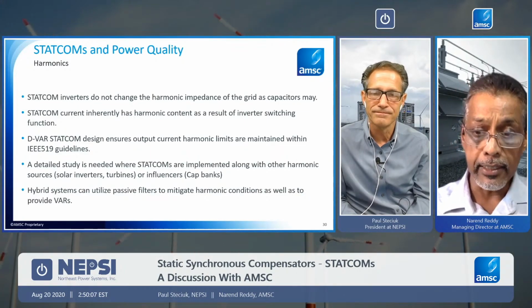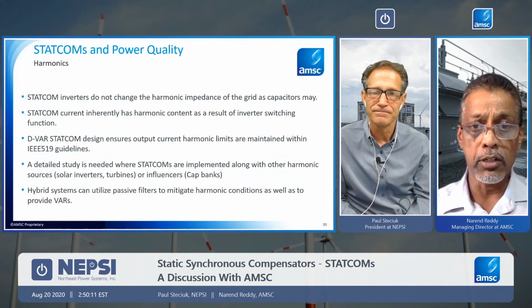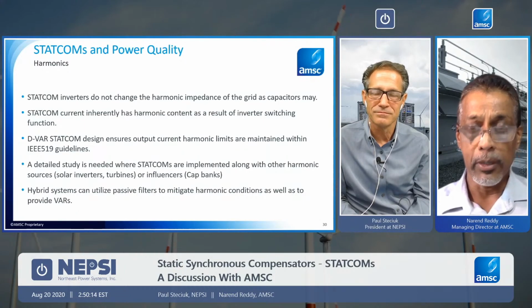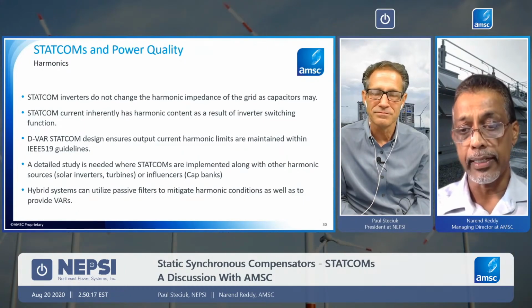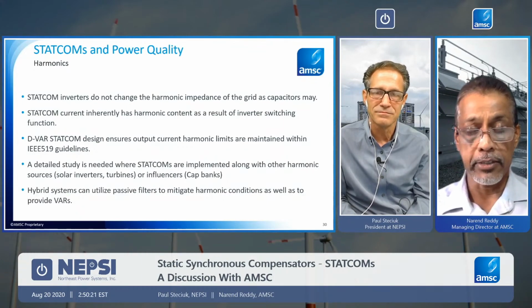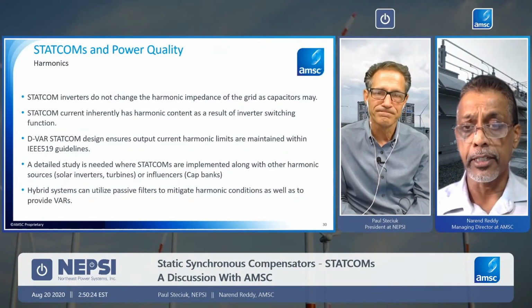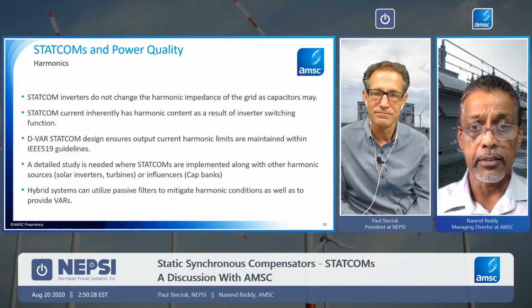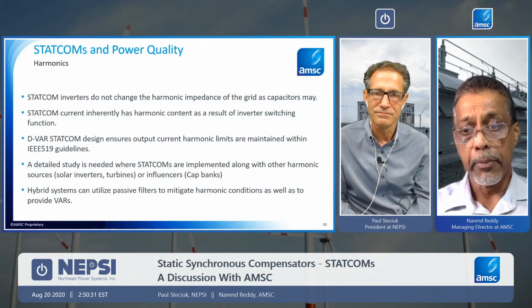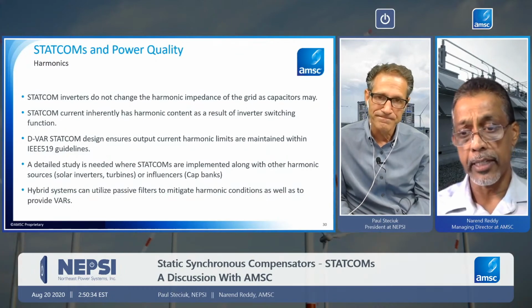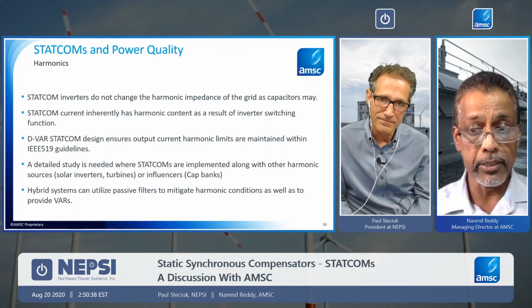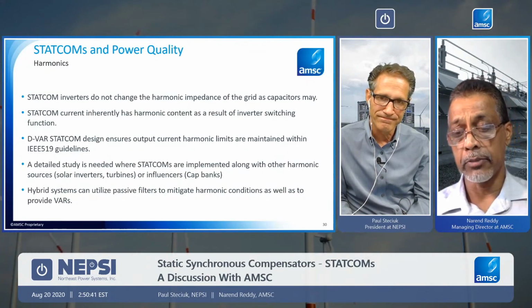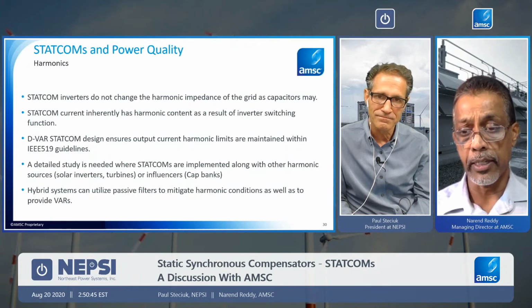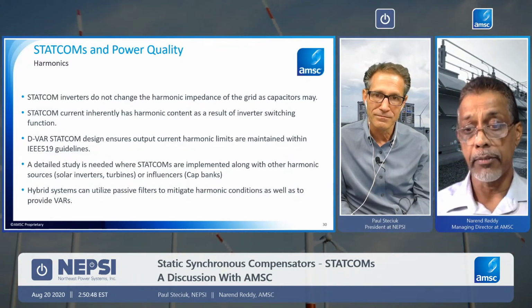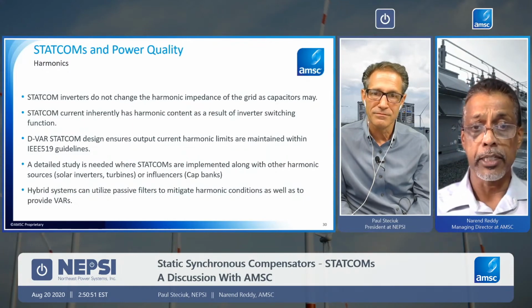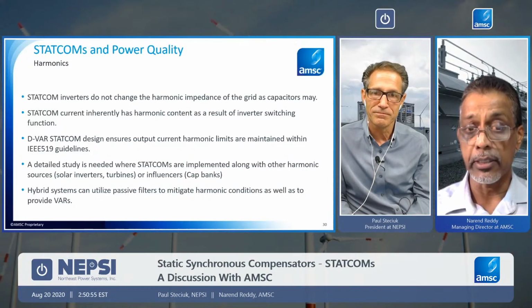Now, I'll make a point here that the STATCOM inverters do not influence the harmonic impedance, so they won't change it, similar to how a cap bank does. A cap bank very easily could create a resonance in the critical 5th, 7th range, but a STATCOM inverter does not change the harmonic impedance. But if there are cap banks as well as other harmonic sources in the grid, let's say at a renewable plant you have turbine inverters that may have certain harmonic characteristics, they may be low, but if there are many of them, you have to look at the overall picture and take all of that into account. A study would be necessary in that way.